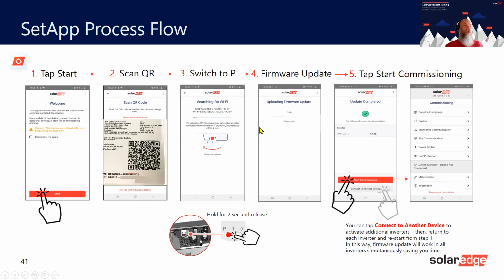So what it does is it uploads the firmware. Once it's finished uploading the firmware, you can walk away from the inverter. You can go and do something else. You don't have to stand in front of it. You just have to leave your phone there for the update. And once it's on the inverter and it shows the update is complete, when it gets to this stage, then you can go into the commissioning.